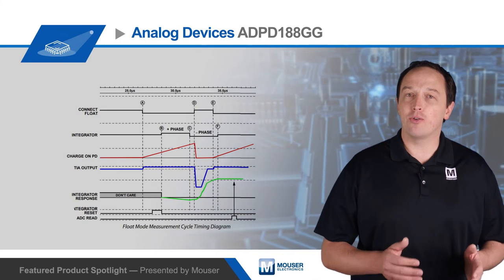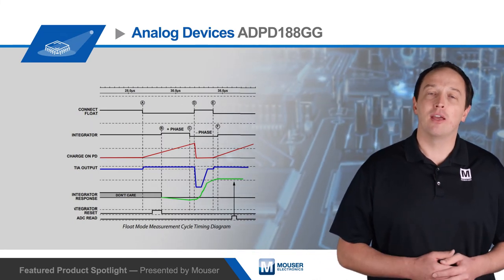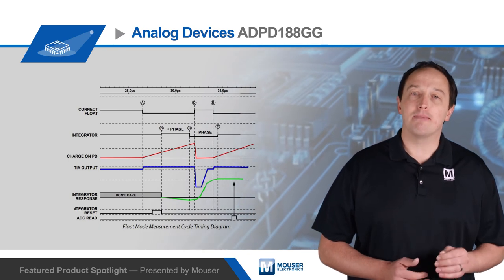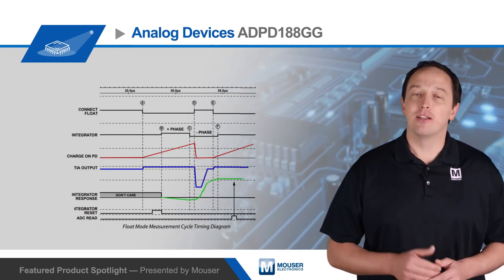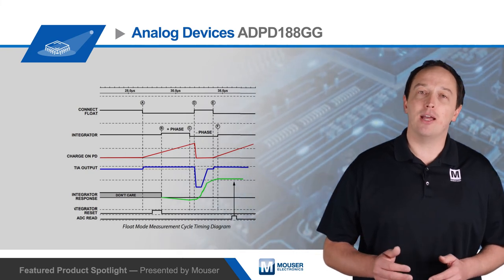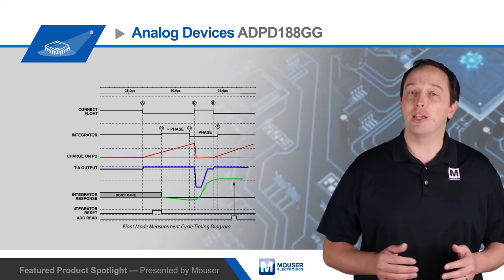After the float time has expired, the photodiode is switched back into the receive path and the accumulated charge is sensed by the ADC. This method maximizes the charge process to minimize the noise in the measurement, and designers can optimize float time and LED drive current to meet application needs.